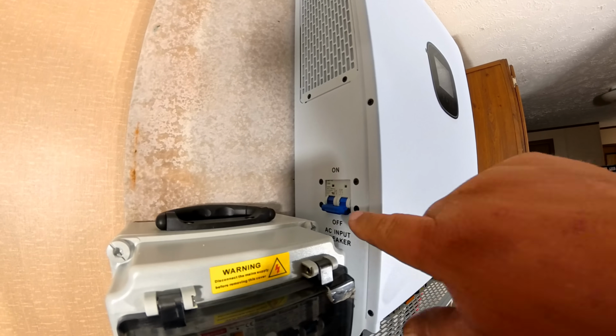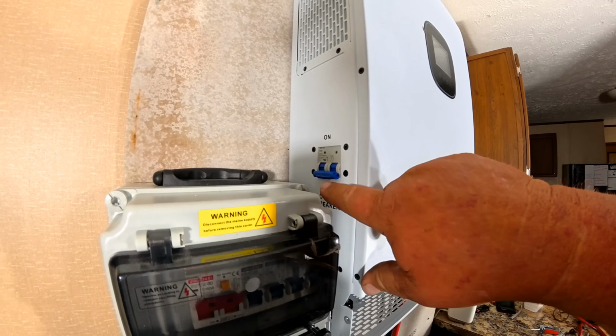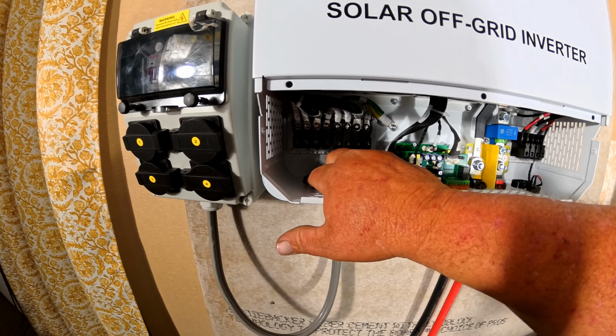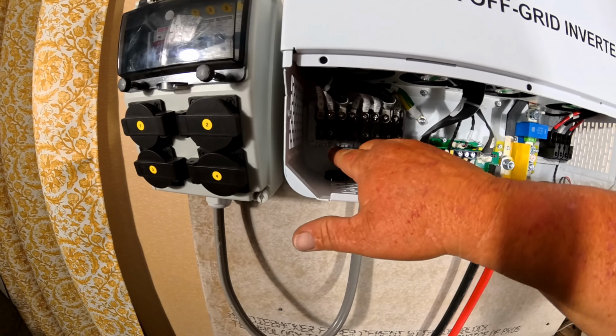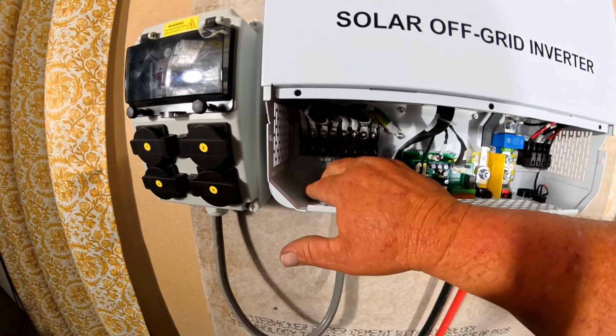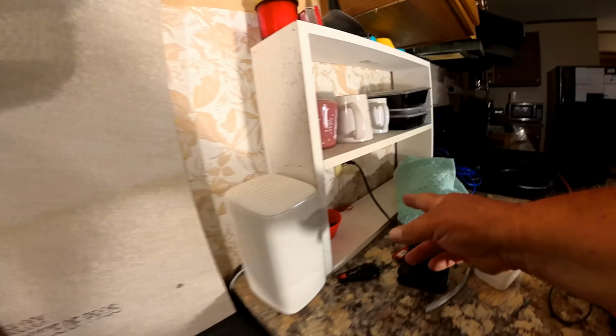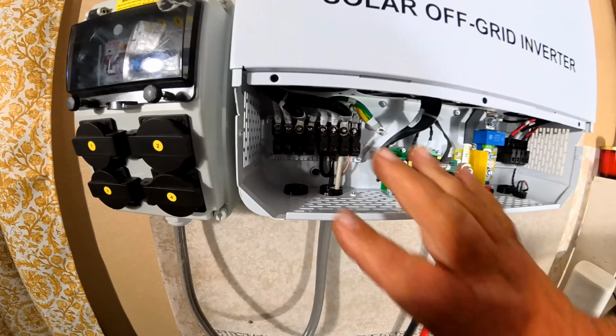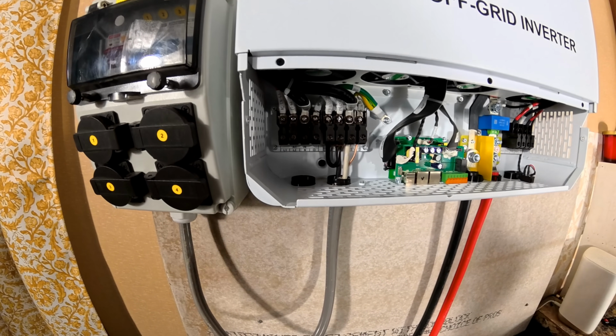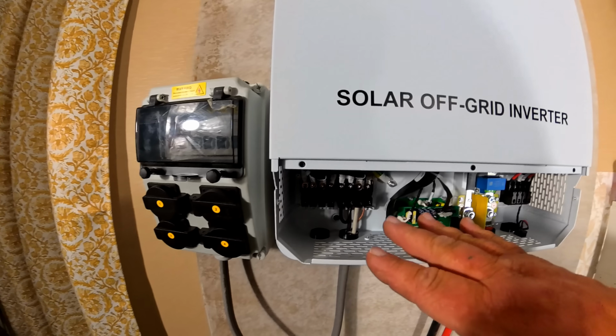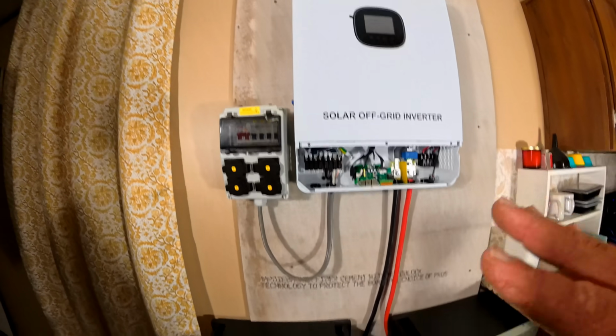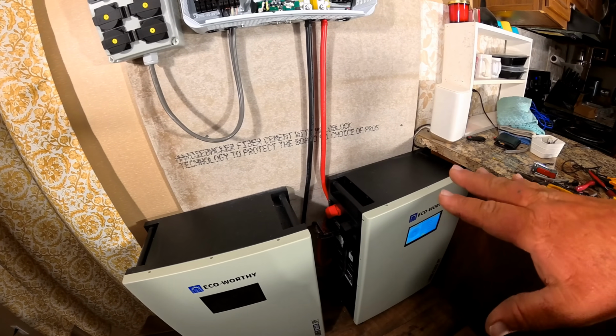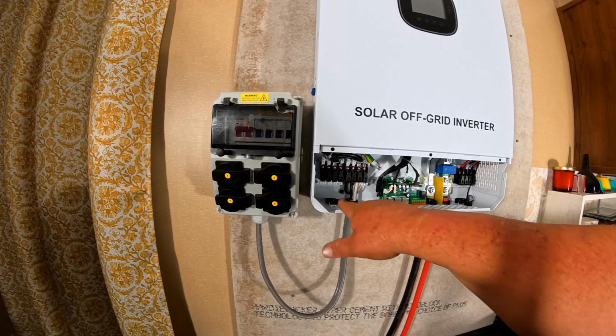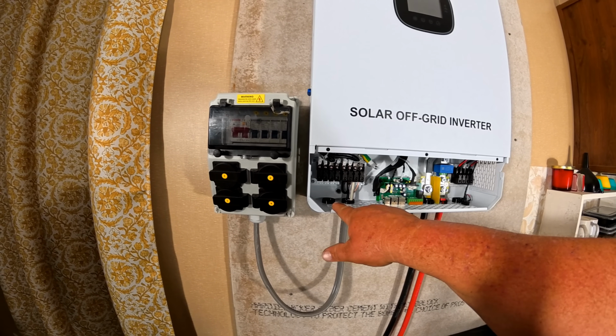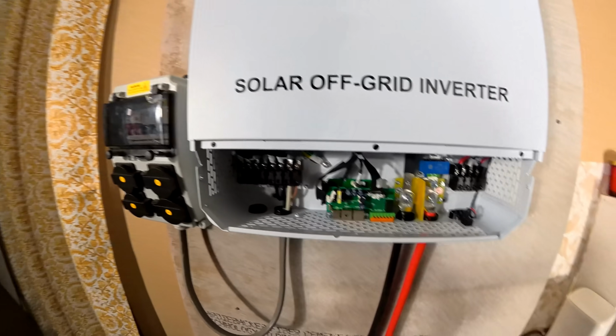Also on the side of this inverter, it does have the AC input breaker. Basically what you're wanting to do is run your generator wiring up into here on your AC input, or you could take a plug receptacle or wiring out of your plug and run it up in here, or take a dedicated wire out of your breaker box and run it up in here. That will give the system a backup, able to charge the batteries when the solar can't keep up. It's either for a grid backup or a generator backup. So yeah, lots of options here.